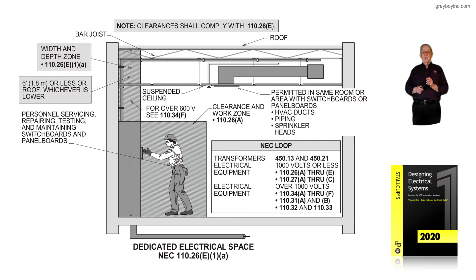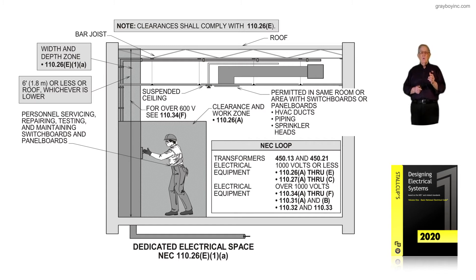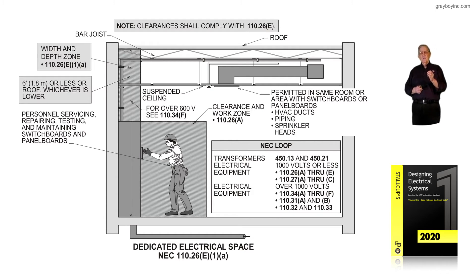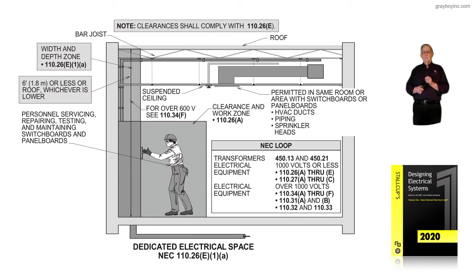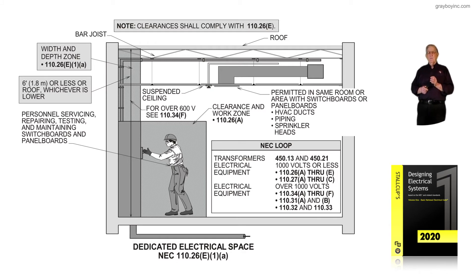It's over a 1,000-volt listing if we use the NEC sections that we will see in the boxed-in information. Notice there are two main sections for transformers, 450.13 and 450.21. In previous illustrations under conditions 1, 2, and 3, we show the transformer with five bullets that show sections that should be reviewed if transformers are present. Those are transformers 1,000 volts or less, rated by NEC that you see in the boxed-in NEC loop information.